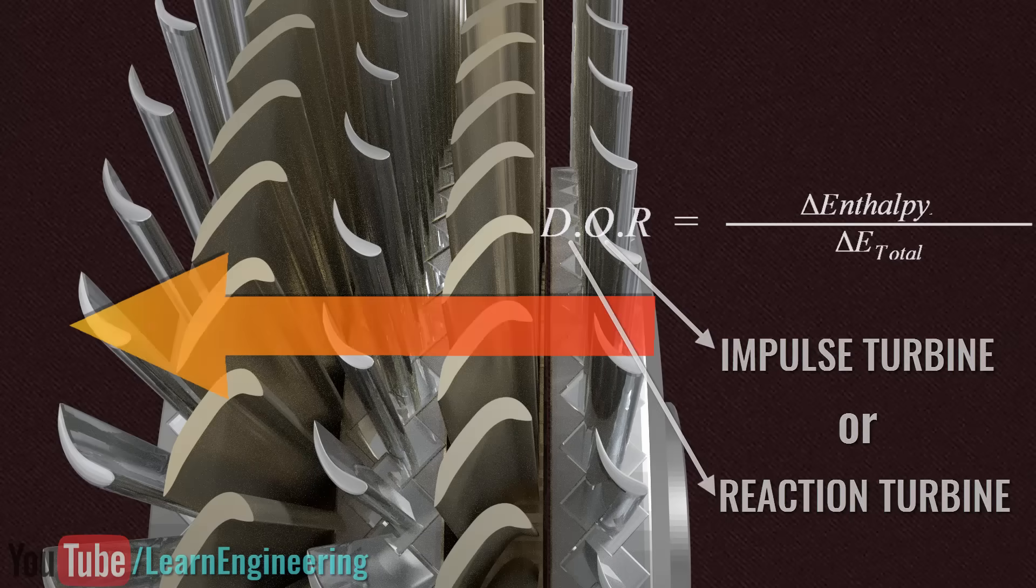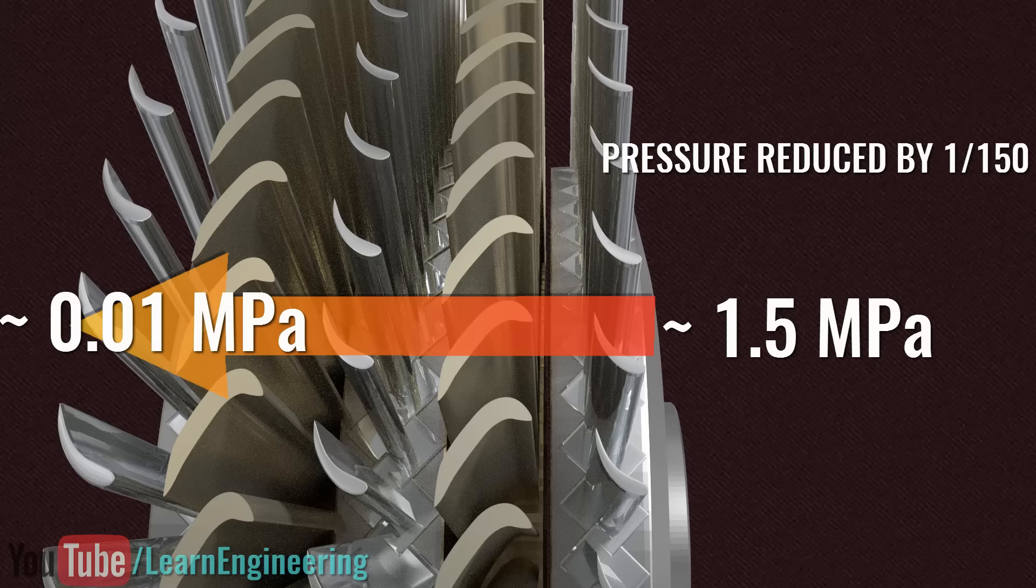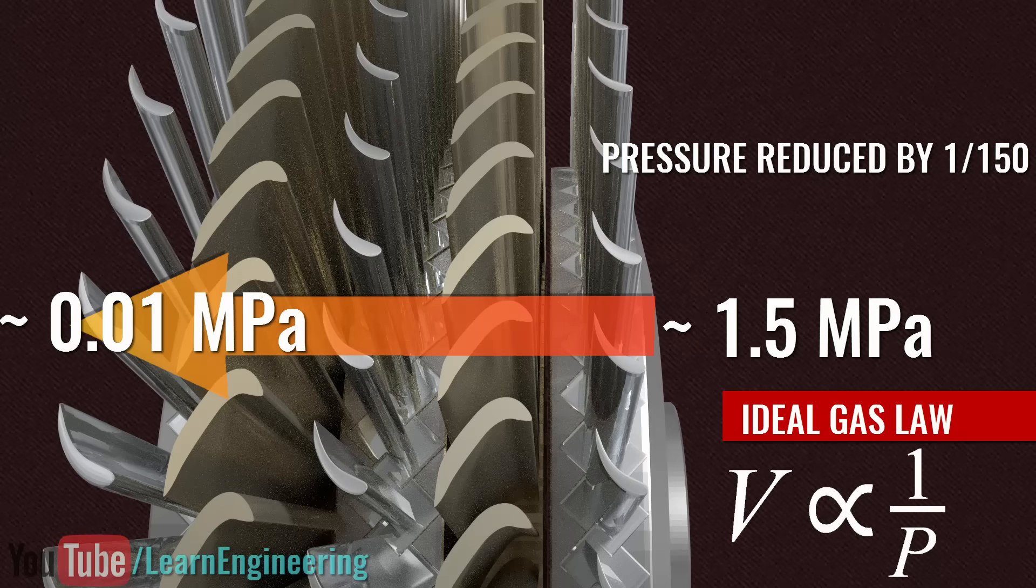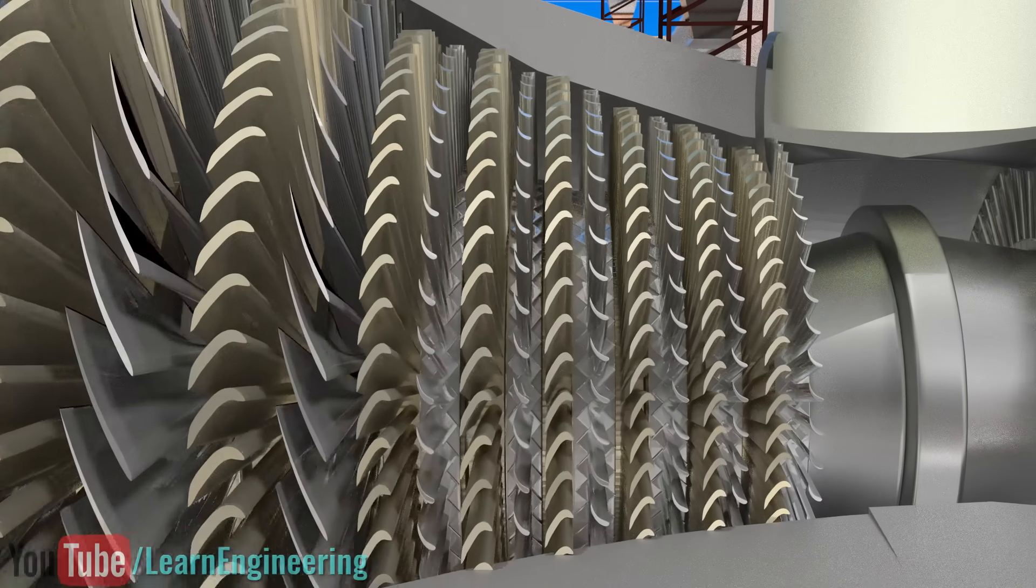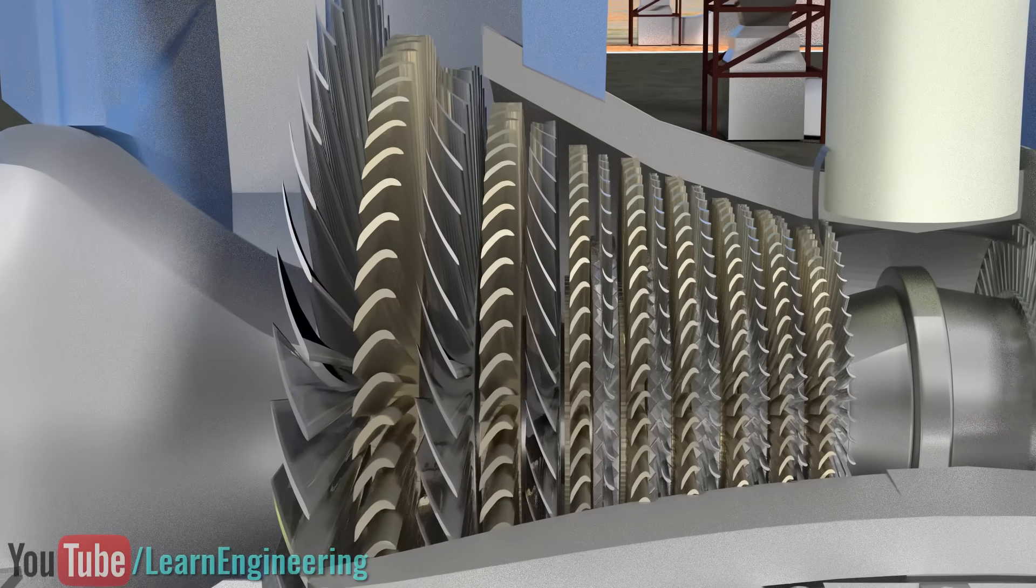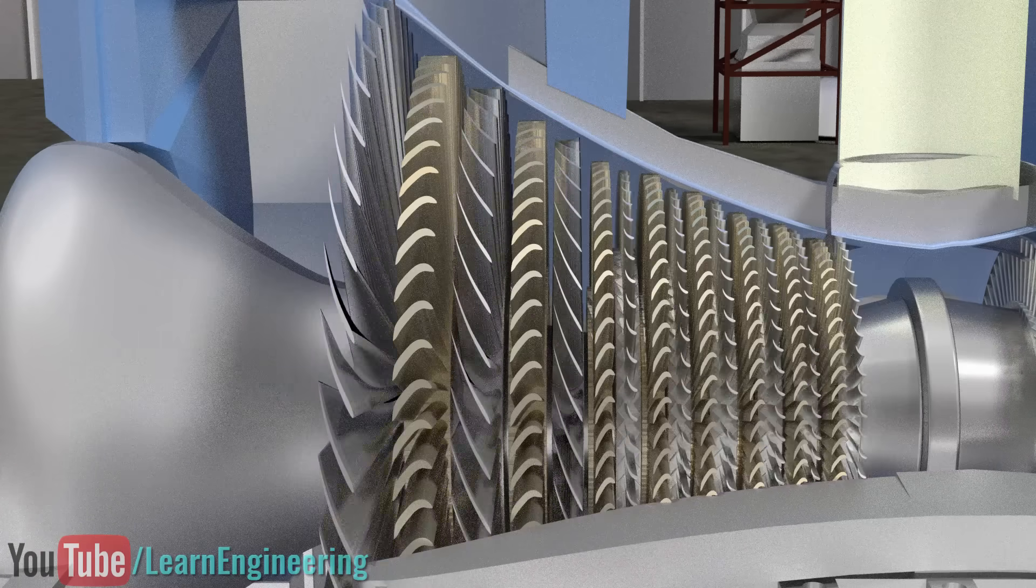As the pressure of the steam undergoes a drastic reduction during steam turbine operation, its volume increases proportionally. To accommodate such an expanded steam, we have to increase the flow area. Otherwise, the flow speed will become too high. This is the reason why the steam turbine blades are too long towards the outlet.